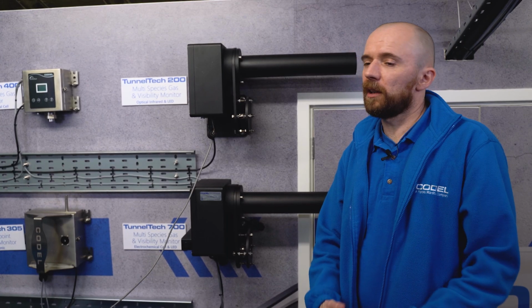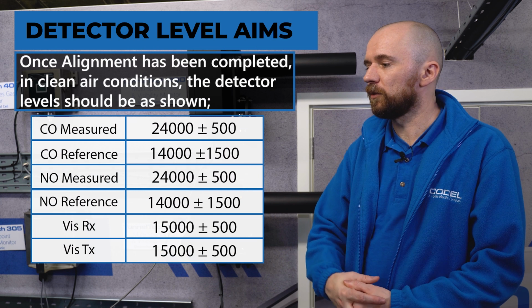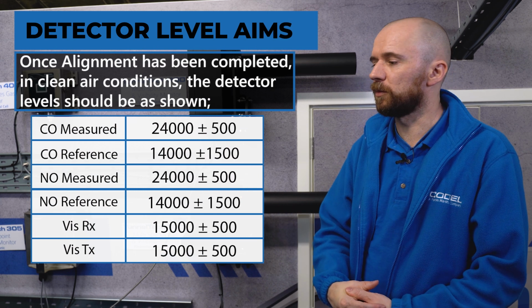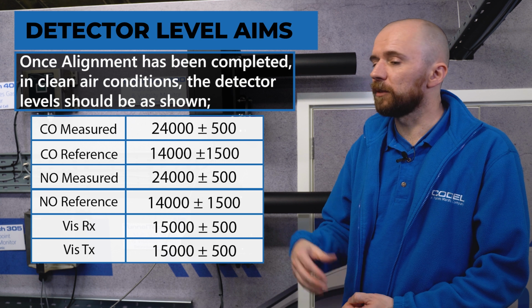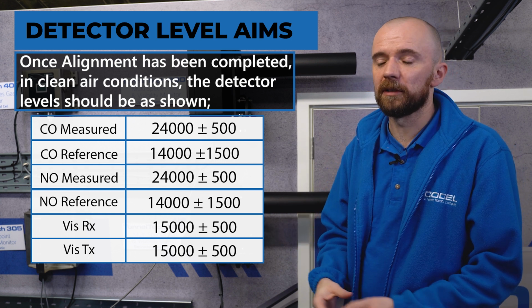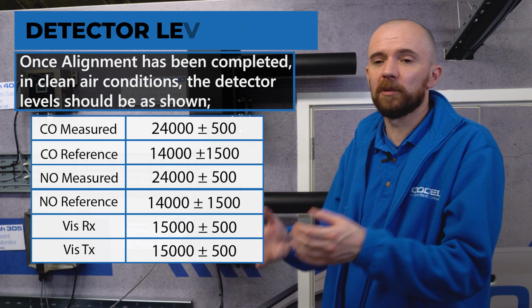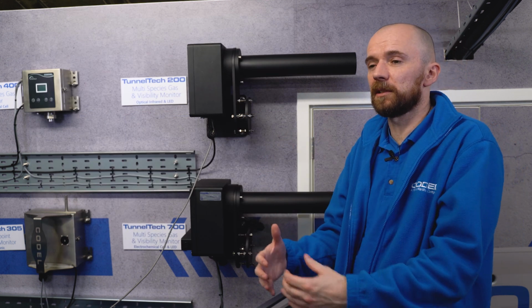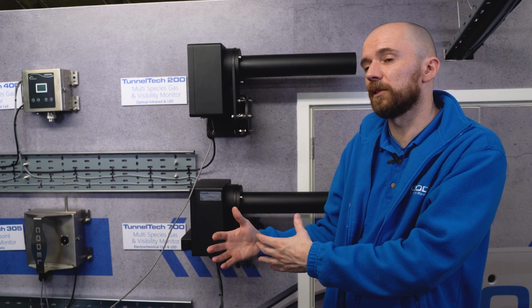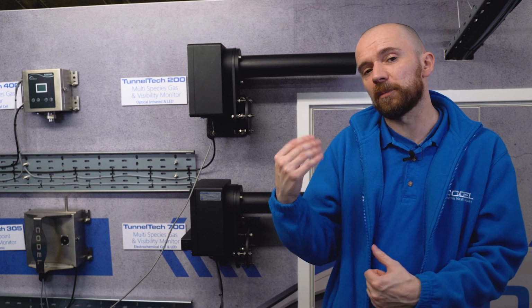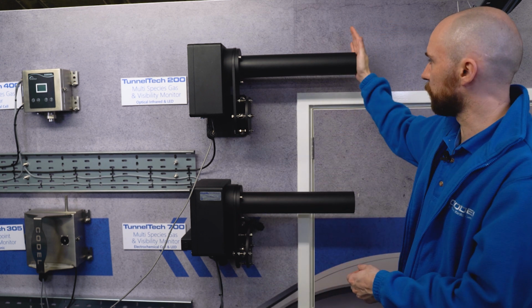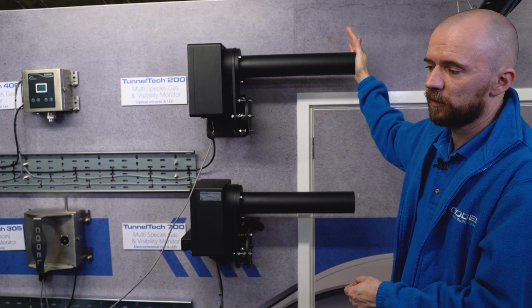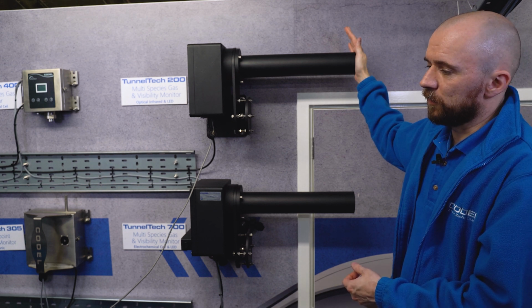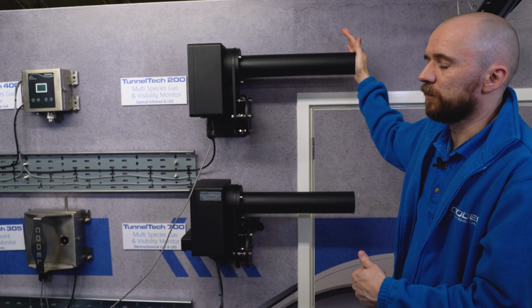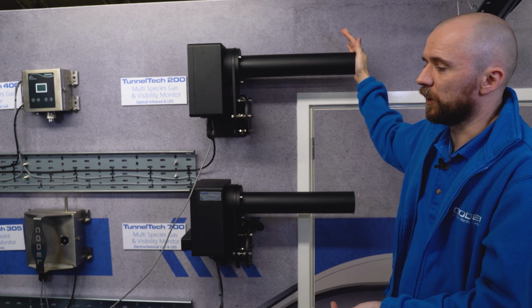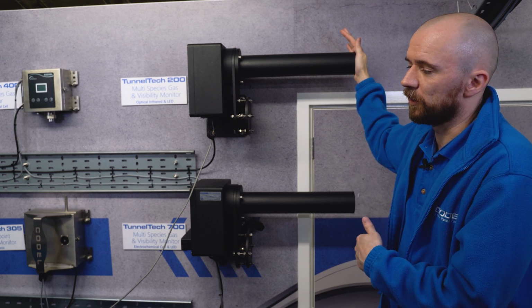So once we've achieved our maximum figure during the fine alignment process, we now need to put the system into a zero calibration, because obviously any changes we've made to alignment will affect detector levels, and then detector levels will obviously affect the response of the system. The easiest way to calibrate this system is just to block the sight tube for about 10 seconds. So the system will see a drop off in detector level, it'll wait a certain amount of time, and then you'll hear a relay click to tell you it's gone into calibration.